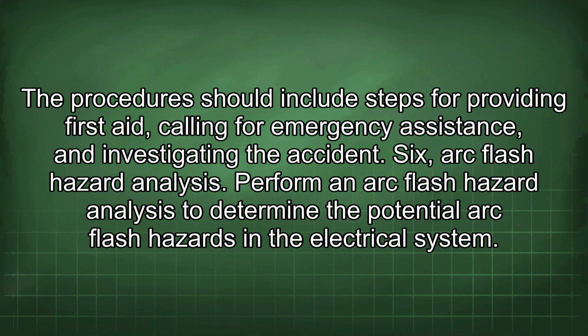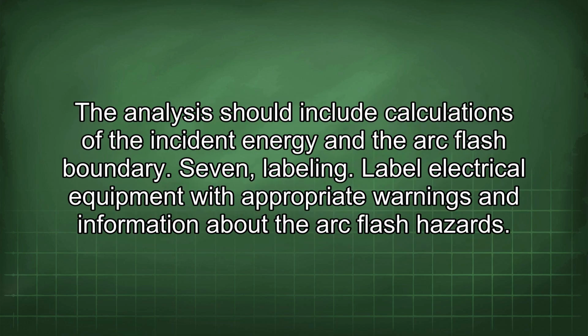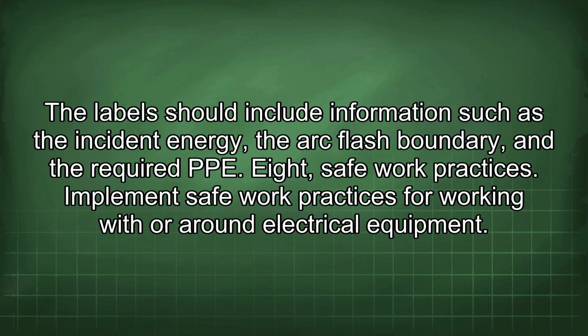6. Arc flash hazard analysis. Perform an arc flash hazard analysis to determine the potential arc flash hazards in the electrical system. The analysis should include calculations of the incident energy and the arc flash boundary. 7. Labeling. Label electrical equipment with appropriate warnings and information about the arc flash hazards. The label should include information such as the incident energy, the arc flash boundary, and the required PPE.